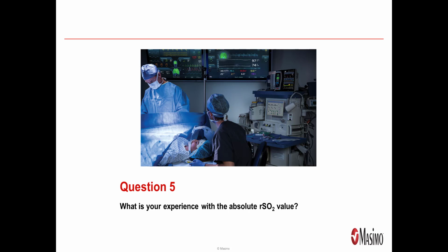So some people have suggested that when you put the electrodes, you might place them in the shape of a letter A, instead of completely horizontal, in order to avoid the frontal sinus. And sometimes you just put them a little bit higher up, and then the value goes back to normal. So that's always important to keep in mind. These very low values, we see them rarely.